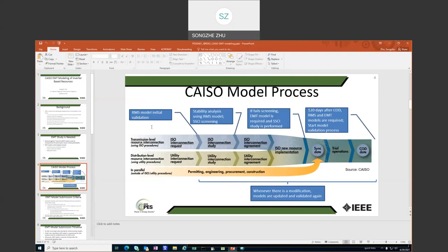It is based on the proximity of the IBR to a series compensated transmission line and based on impedance scan. If the SSCI risk is identified, then we would require the EMT model and perform an SSCI study before the generator can synchronize to the grid. If the screening doesn't identify the risk, then we would require the EMT model 120 days after COD, after commercial operation. The purpose is that at that time we can get a very good as-built model that reflects what's actually installed and set up in the field. Post COD is when the very thorough validation process starts.